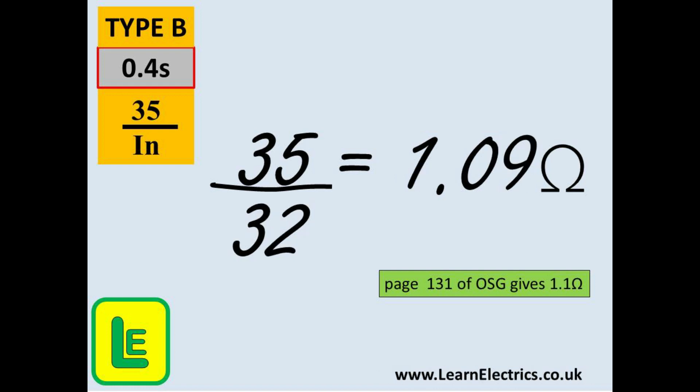And finally for type B breakers let us try the ever popular 32 amp device. So 35 divided by 32 gives us 1.09 ohms. The book gives us 1.1 ohms. This is close enough and in fact some test sheets do actually quote 1.09 ohms. Most times your circuit ZS will not be anywhere near these maximum figures so you will not have to worry about any small differences.